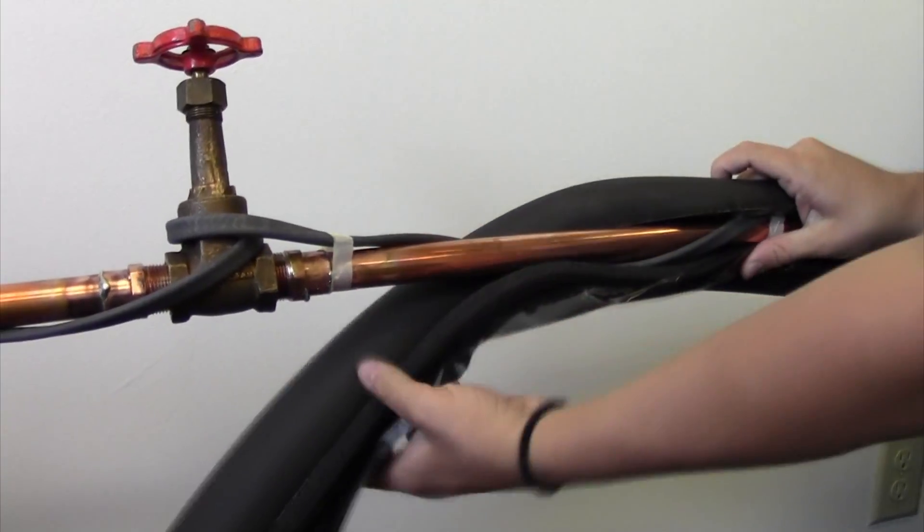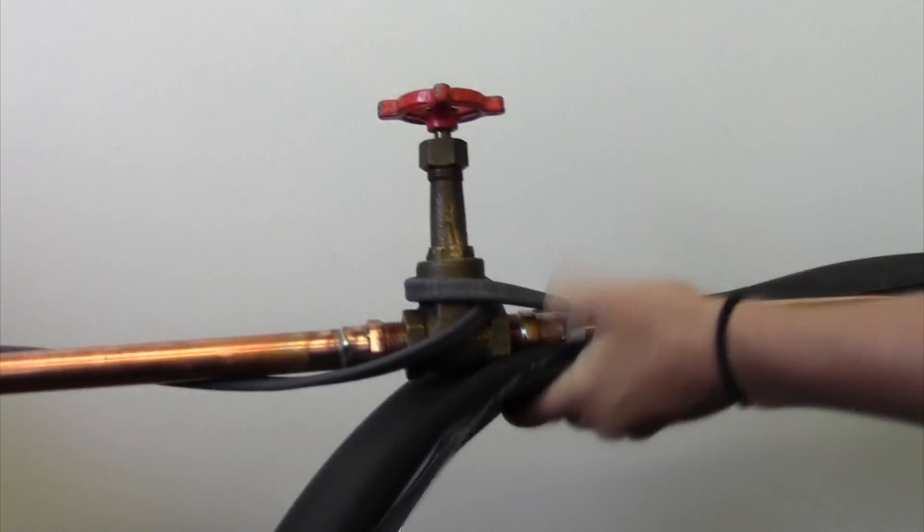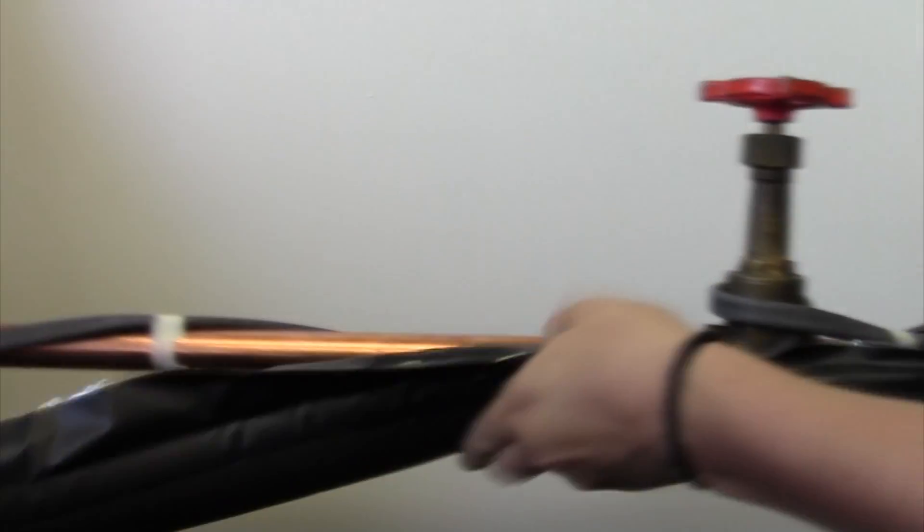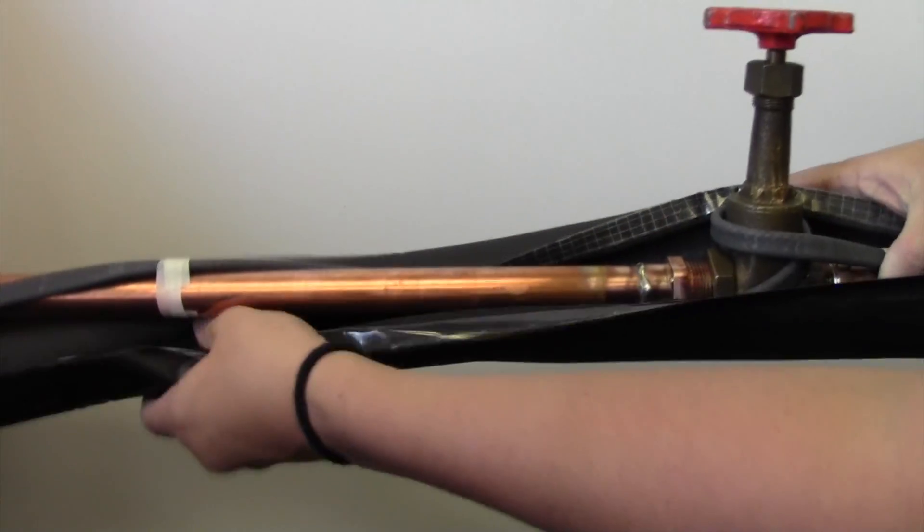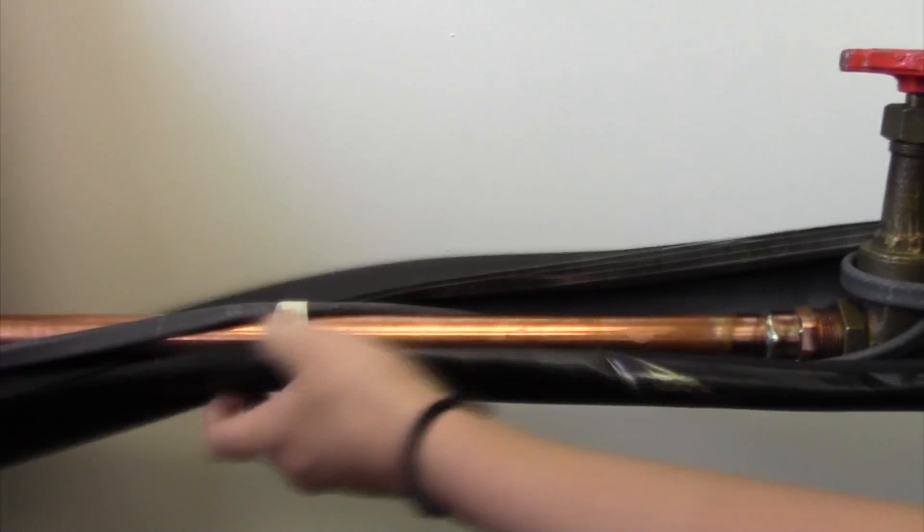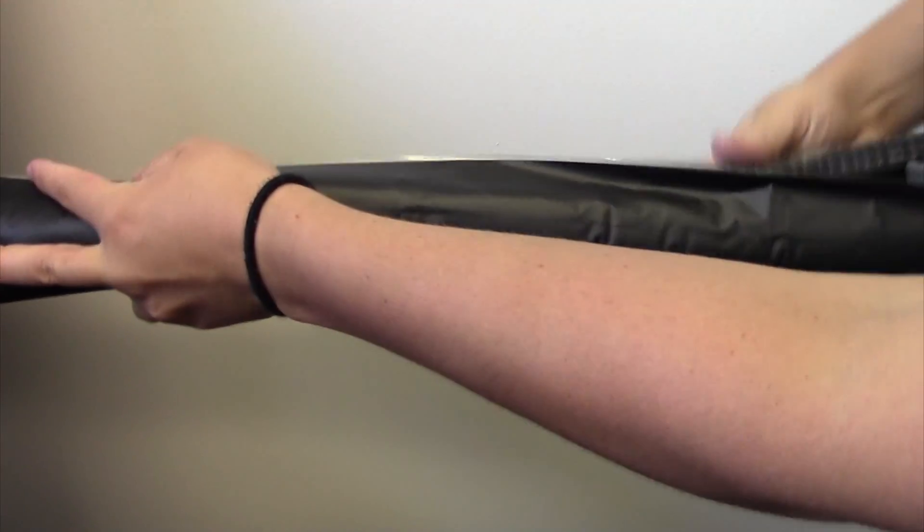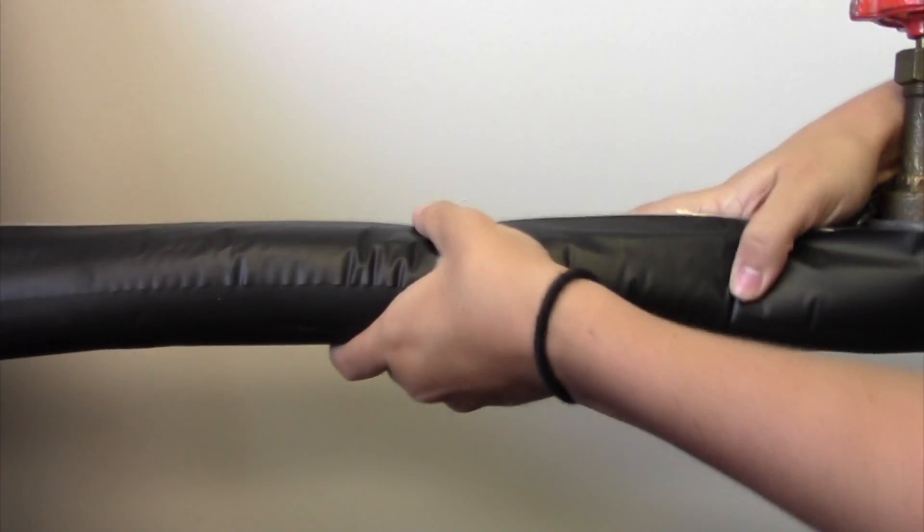After installation of the heating cable, cover the secured cable and the pipe with a 3 quarter inch to 1 inch flame resistant insulation like Insiloc insulation. Insiloc insulation has a convenient sealing flap that will allow for protection of the insulation joint and a seamless fit.